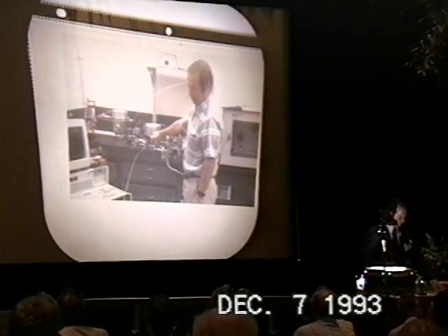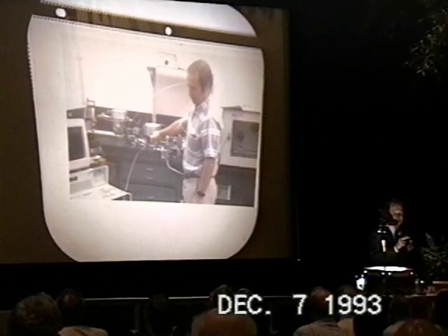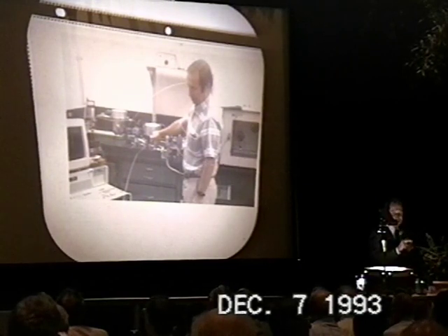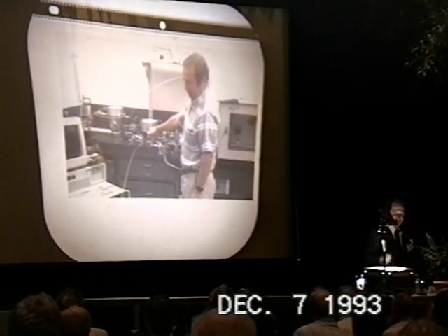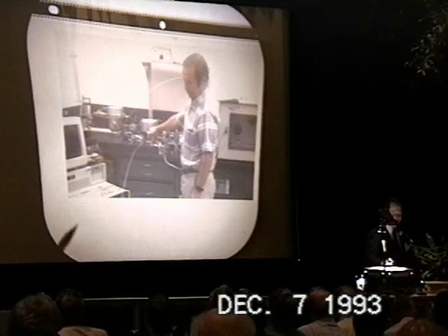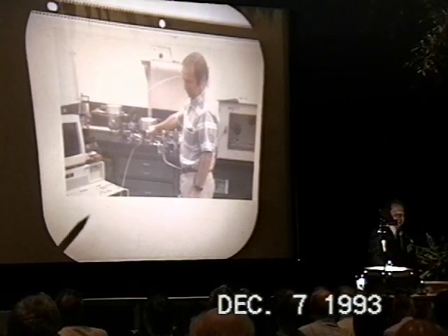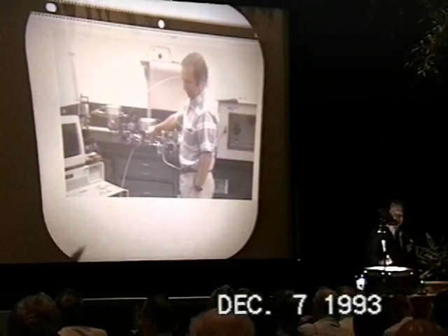This is a picture of the instrument we use, which is simply a 2-liter ionization chamber. It's not a very good picture of the ionization chamber, but it is a good picture of me, so I showed it here. It's at least as good as they get. The ionization chamber is actually a center electrode, which is a fin, not a single electrode, surrounded by a cylinder which is held at about negative 100 volts.